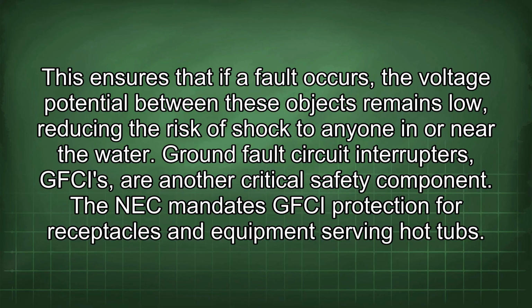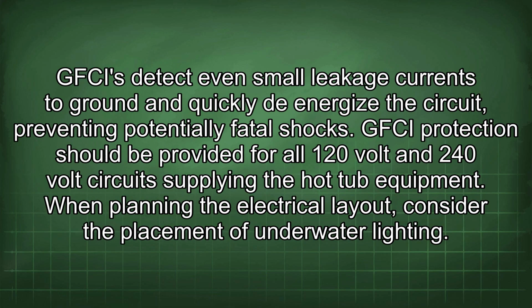This ensures that if a fault occurs, the voltage potential between these objects remains low, reducing the risk of shock to anyone in or near the water. Ground fault circuit interrupters, GFCIs, are another critical safety component. The NEC mandates GFCI protection for receptacles and equipment serving hot tubs. GFCIs detect even small leakage currents to ground and quickly de-energize the circuit, preventing potentially fatal shocks.